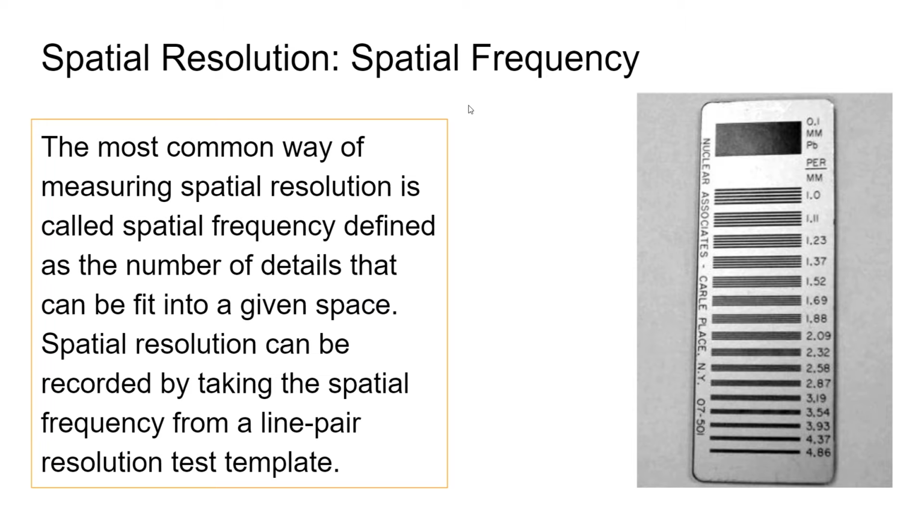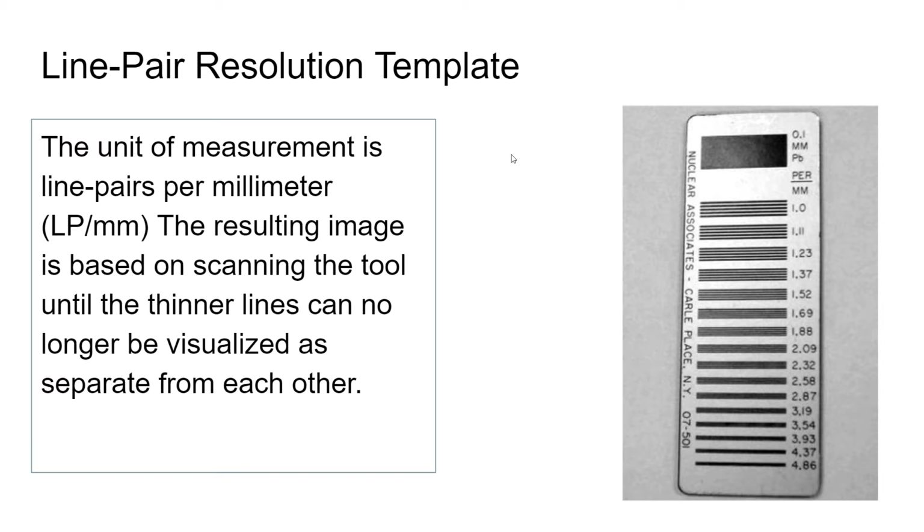And we can look at what's known as the spatial frequency. More on this word in a second. As we've discussed in previous labs and classes, we measure this by counting, literally, line pairs per millimeter. The more line pairs that you can count, the better your spatial resolution is. Another way to say this is the better chance you have of resolving an object that you might be looking for. At a certain point, you can't resolve an object.